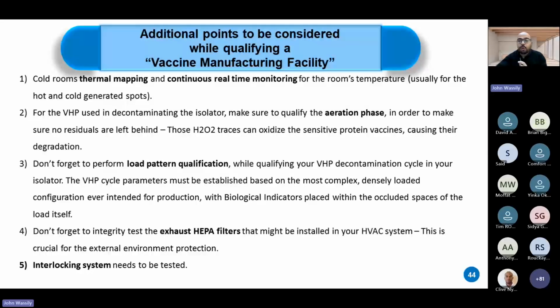It's important to know that while qualifying the VHP decontamination cycle in your filling isolator, you shall qualify it under worst case conditions, putting all the maximum loads that could be present inside the isolator. This load could hinder the H2O2 from reaching all critical parts, which can compromise sterility and asepsis of the environment.